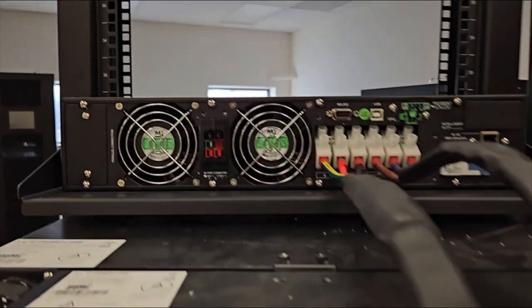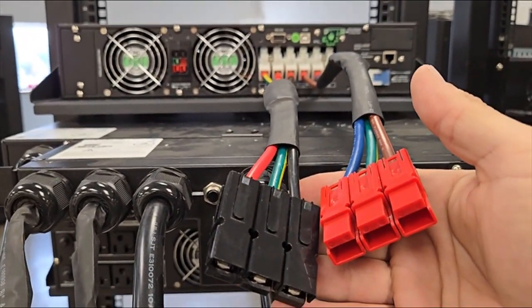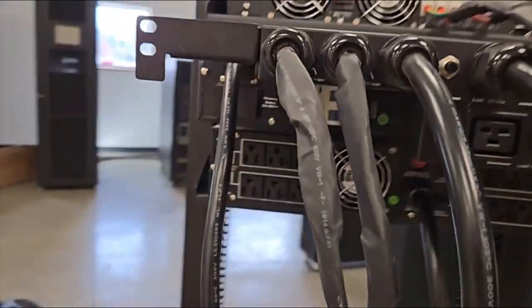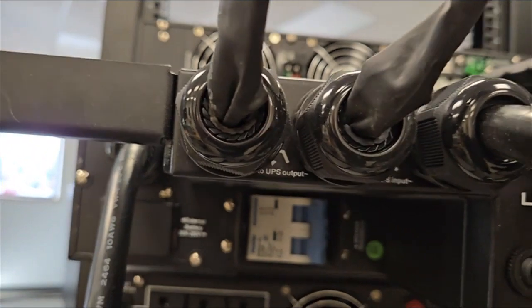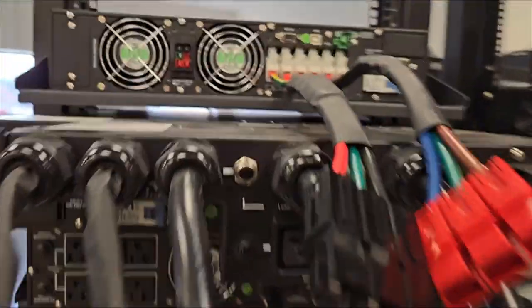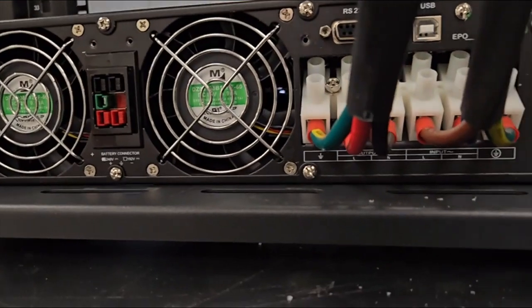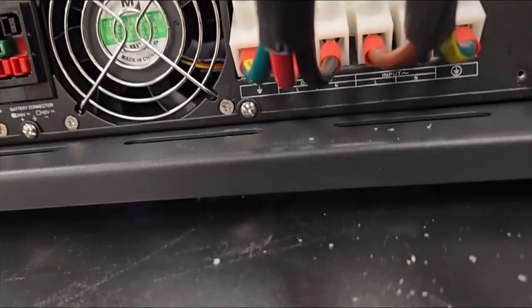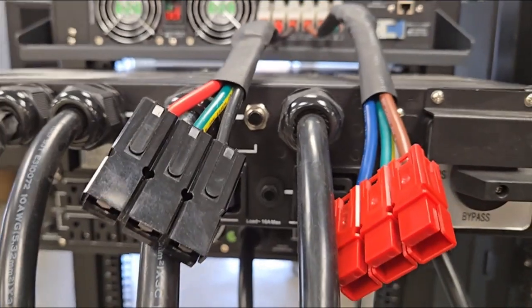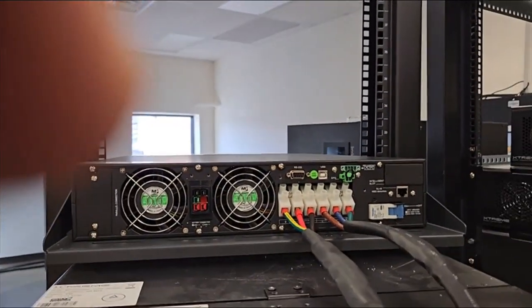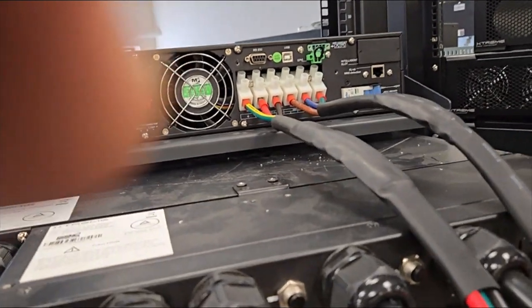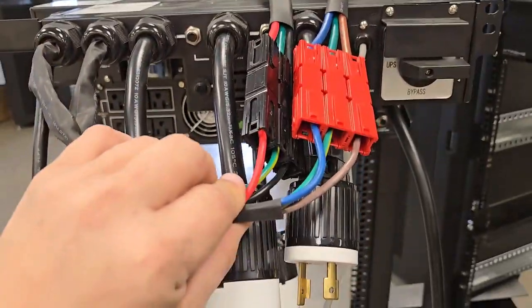These wires that get installed in the back of the UPS come with the bypass, and they mate up. You can see it says UPS output and UPS input, and that matches red and black. And then we've got input and output on the back of the UPS. So I have those matching red to red, black to black, and so I've made those connections.